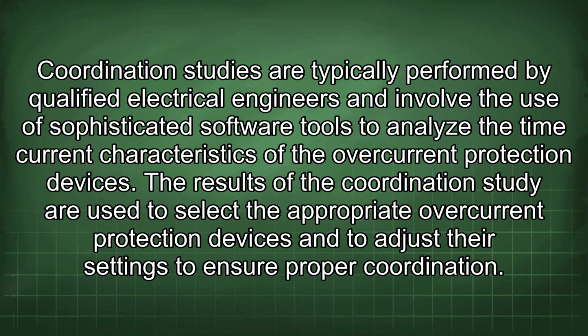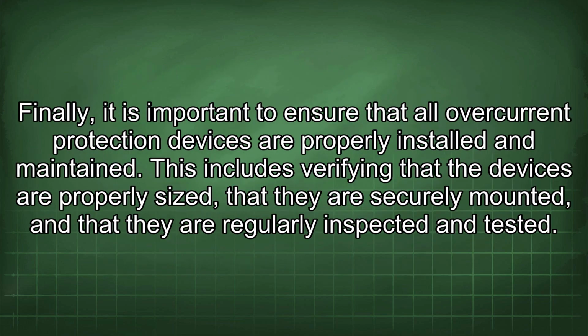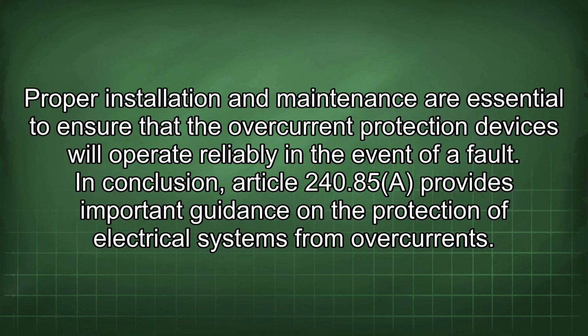The results of the coordination study are used to select the appropriate overcurrent protection devices and to adjust their settings to ensure proper coordination. Finally, it is important to ensure that all overcurrent protection devices are properly installed and maintained. This includes verifying that the devices are properly sized, that they are securely mounted, and that they are regularly inspected and tested. Proper installation and maintenance are essential to ensure that the overcurrent protection devices will operate reliably in the event of a fault.